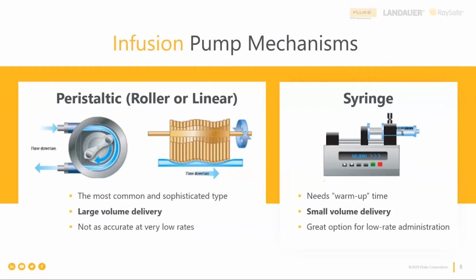The peristaltic ones, just like Jerry mentioned, do the continuous flow. So the way they work is that as the roller turns, or as the fingers in the linear peristaltic mechanisms move, the part of the tube that is under compression is pinched closed, thus forcing the fluid to move through the tube into the patient's vein on a continuous basis. Today, that is the most sophisticated mechanism. It allows for delivery of large volumes of fluid, and it is most commonly used in delivering nutrition or in patient-controlled analgesia.